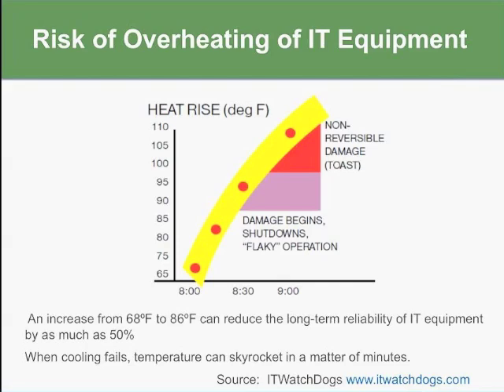And when cooling fails, temperature can skyrocket in a matter of minutes, as we saw in one of Dan's graphs. Now, it's not really the problem of high temperature per se, because ASHRAE has come out with new standards for IT equipment saying that they can handle 80 degrees plus in the equipment. It's actually the consistency of the cooling. So it's a matter of vacillating temperatures significantly that does the damage to the equipment, not necessarily the high temperatures per se. And we'll talk a little bit more about that later.